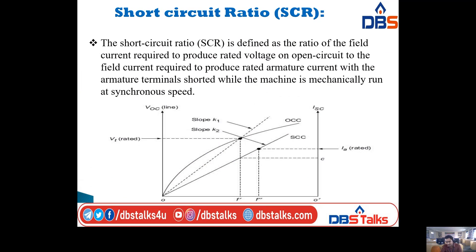Short circuit ratio (SCR) is defined as the ratio of the field current required to produce rated voltage on open circuit to the field current required to produce rated armature current with the armature terminals shorted while the machine is mechanically run at synchronous speed.